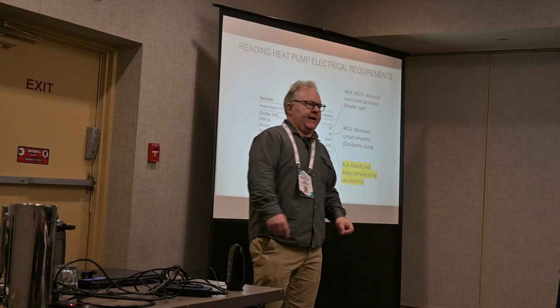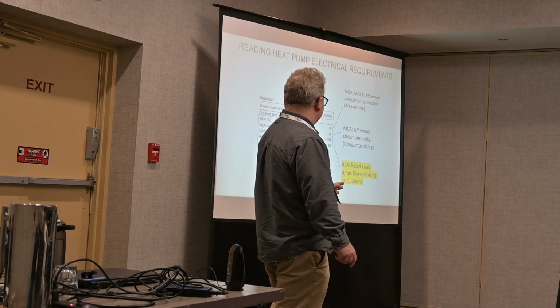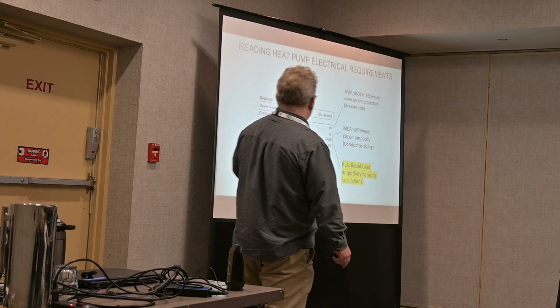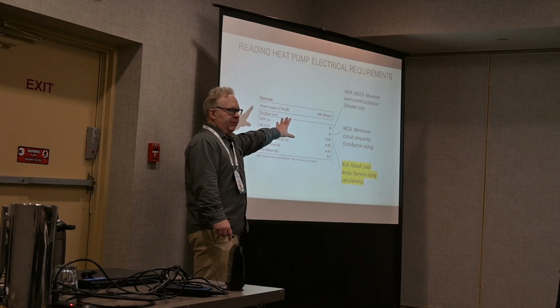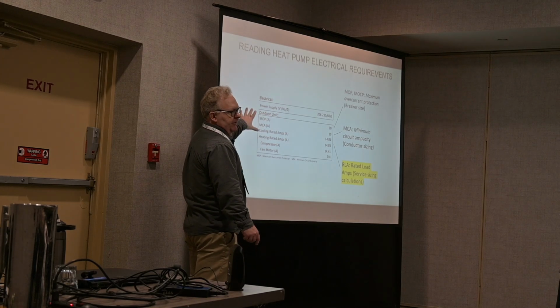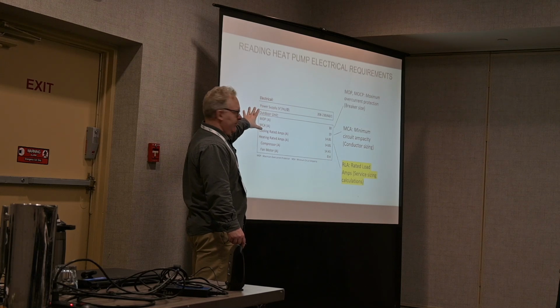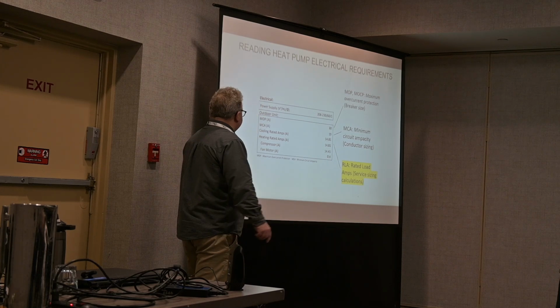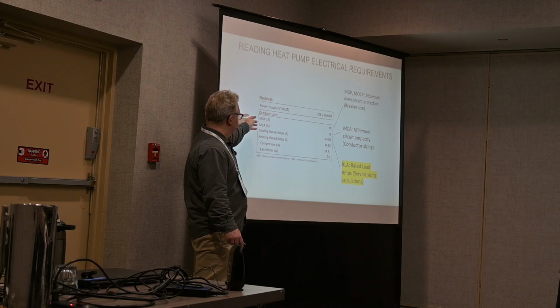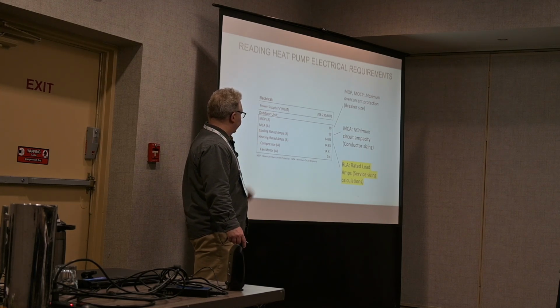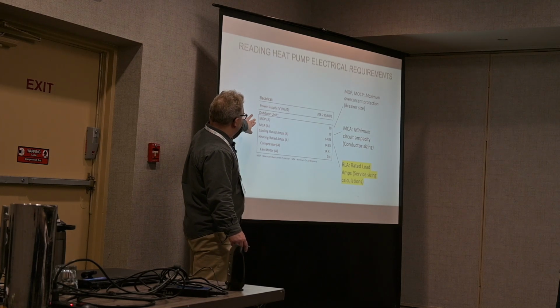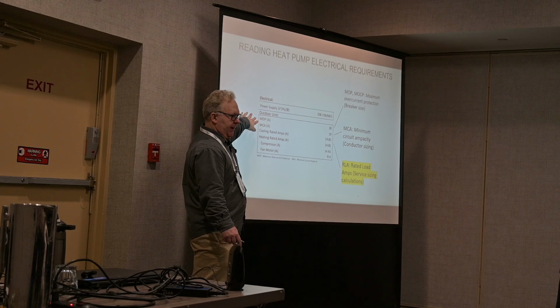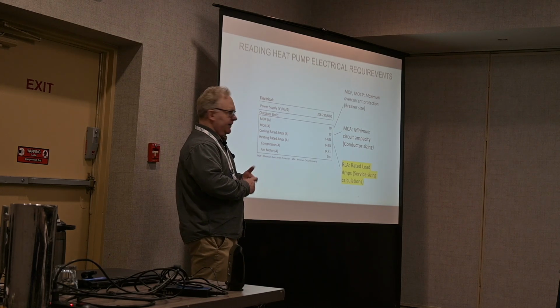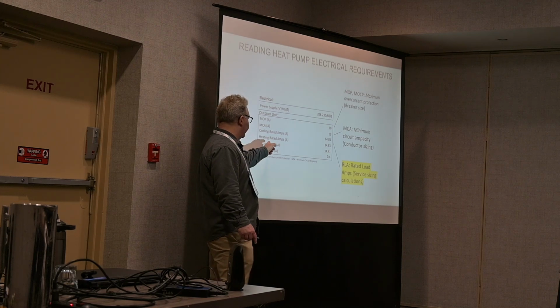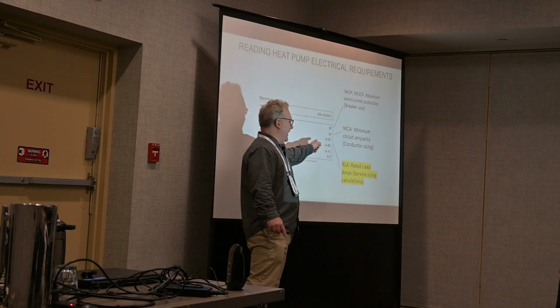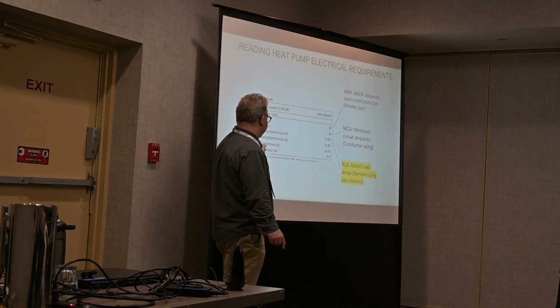Now, when we go to think about adding a heat pump to this system, we need to know what to put in for that. And so here, usually I'm doing this at the design stage, so I'm looking at a submittal. I'm not looking at the nameplate on the unit. By that point, it's a little bit late in the game. And you'll see multiple electrical ratings for this. The MOP and the MCA we'll talk about a little bit later. Those affect the breaker and the conductor size that you use. But for this calculation, what we really want to look at are our rated amps. This is what factors into this calculation.